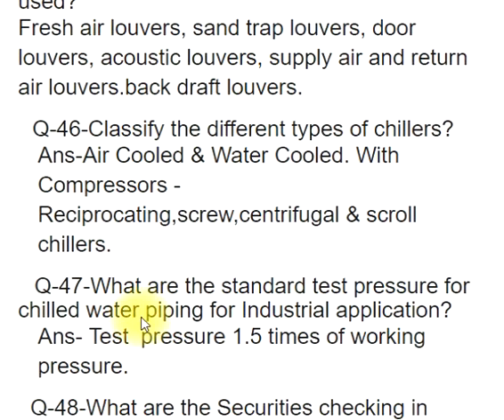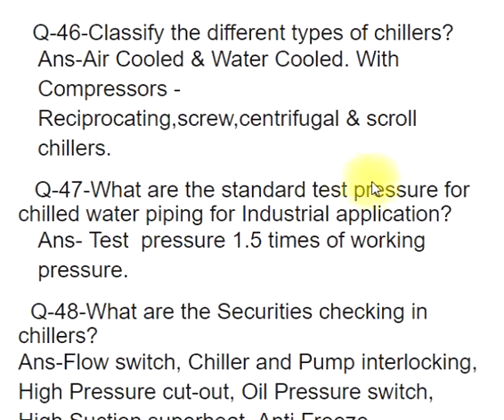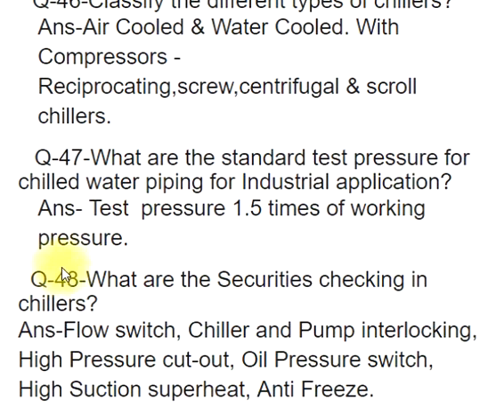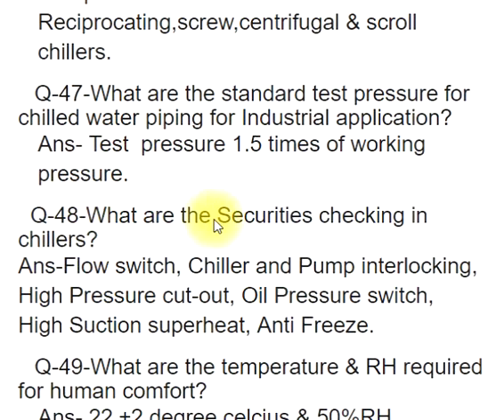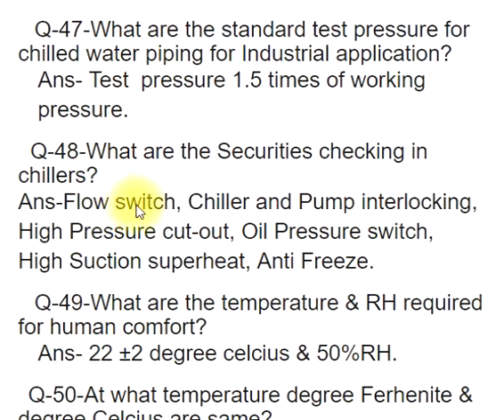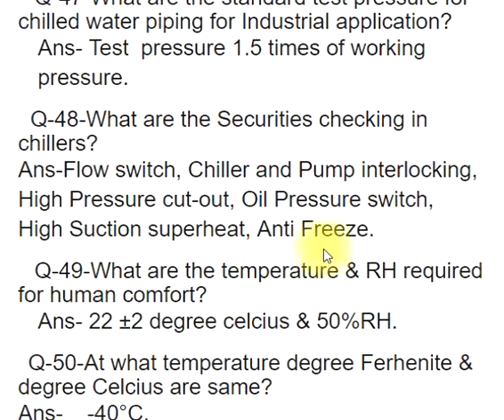Q47: What are the standard test pressures for chilled water piping for industrial application? ANS: Test pressure is 1.5 times the working pressure. Q48: What are the securities checked in chillers? ANS: Flow switch, chiller and pump interlocking, high pressure cutout, oil pressure switch, high suction superheat, antifreeze.